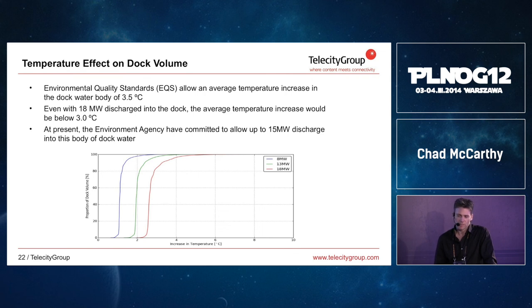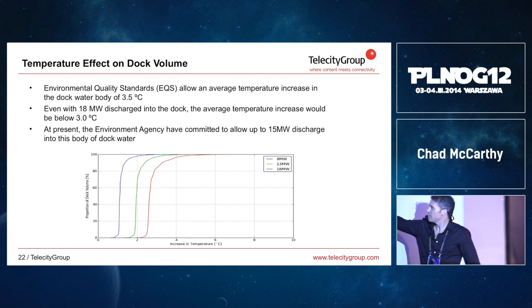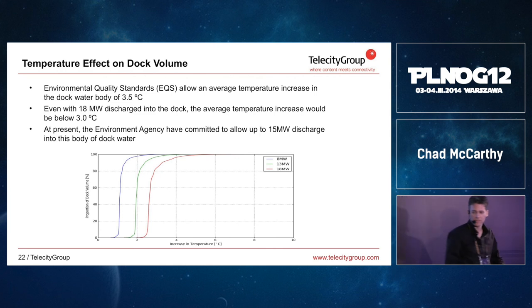Here we have the traces which indicate the average temperature contribution. So the 5 degree temperature increase you saw is right at the top of the diagram here. And that's how we can tell that it's only at the surface of the water and not at the average depth. The average temperature change is under 2 degrees. If you look at the green trace, the red trace is an absolute maximum. The green trace is close to the allowable figure according to the Environment Agency, and the blue trace is really what we're looking at realistically building. So you can see that we're only affecting the temperature of the dock by around 1 degree.